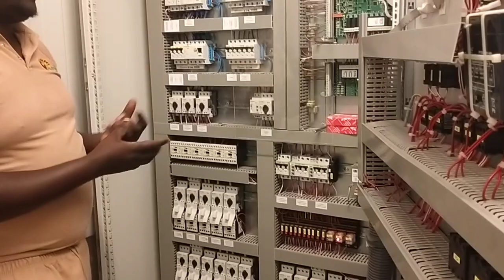It's also important to note that somewhere here we have a timer, and also here we have a timer. This timer is controlling the board. Inside the board we have a fan which regulates the environmental condition of the MCC, and that is regulated by that timer. Then you have this other timer which sets other parameters controlling our loads. Depending on your application, you may have numerous timers inside your MCC, but in our case we only have two.